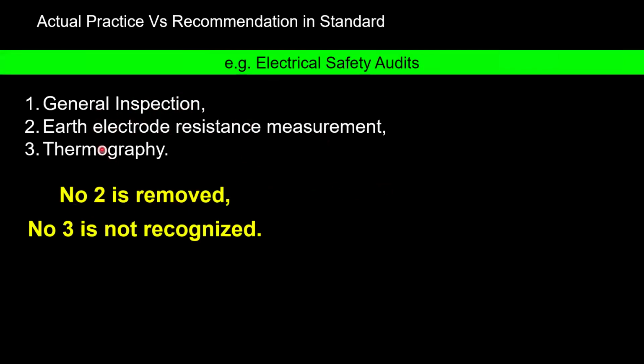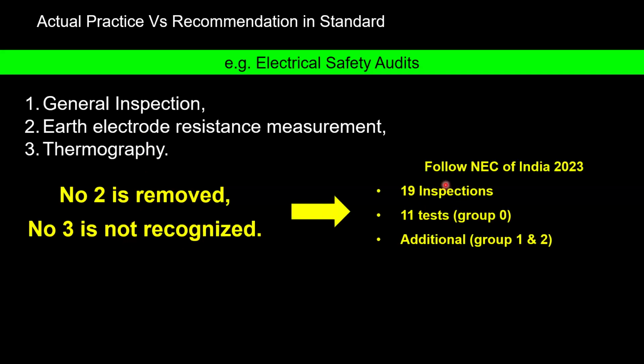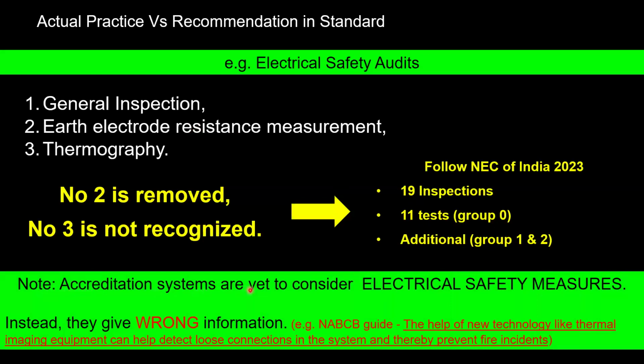Serial number 2, earth electrode resistance measurement, was removed from the standard a few years back. It is removed means you don't need to; if you want, you can do it, but don't expect safety from that. Number 3, thermography is not recognized as a safety measure in the National Electrical Code for a hospital. What we should do? The NEC recommends 19 inspection points and 11 tests in group 0 or general locations of a hospital. Then additional verifications are required in group 1 and group 2 locations. You are supposed to carry out all these inspection processes. It is not like somebody coming and walking around, making a general inspection, testing a few earth electrodes and doing thermography. Unfortunately, the accreditation systems in India are yet to consider electrical safety measures.